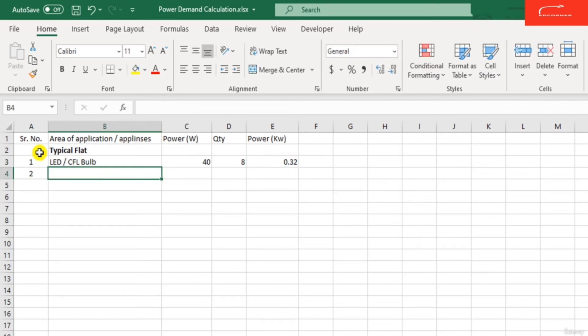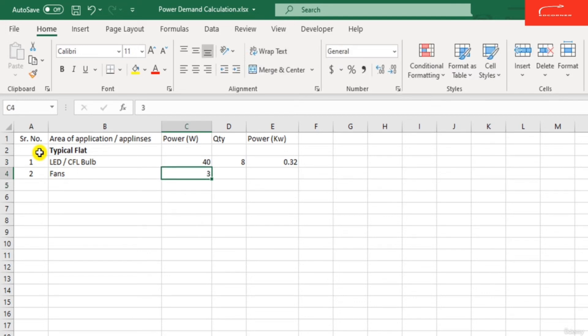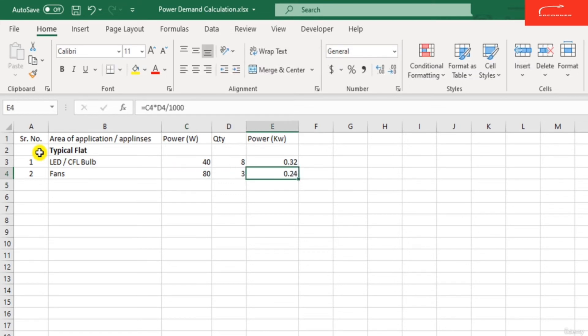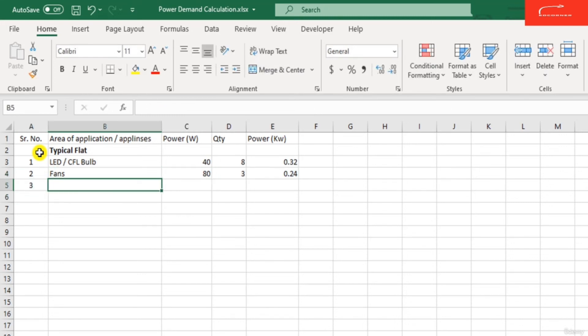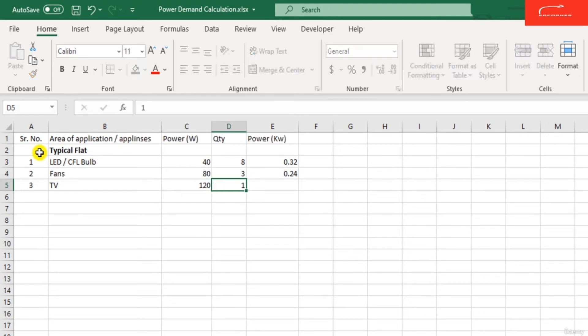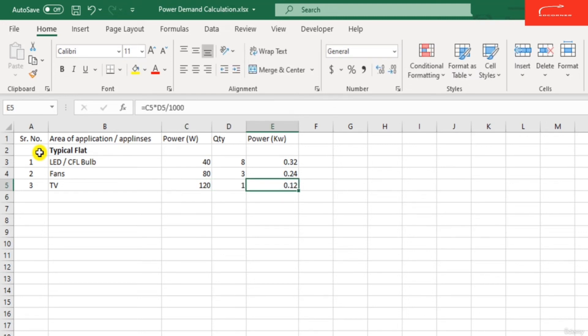Appliance number 2 is fans. If in a typical flat there are 3 fans, the power required for a typical fan is 80 watts, so the total is 0.24 kilowatt. Next, if we need to run a TV in the typical flat, the power required is around 120 watts and the quantity is 1, so the total power required for the TV is 0.12 kilowatt.